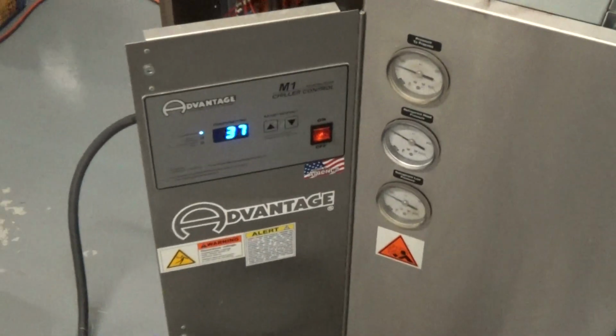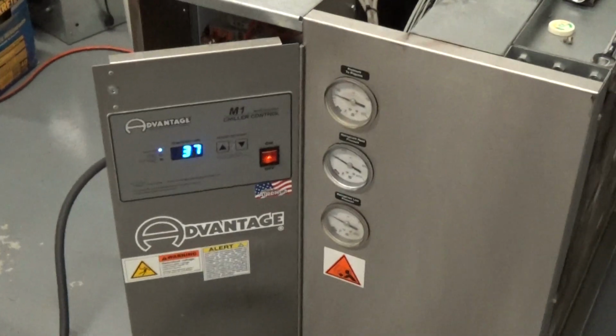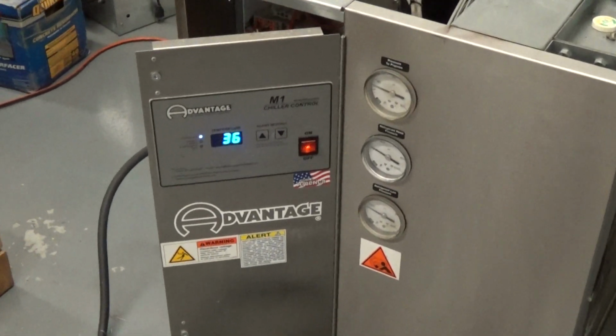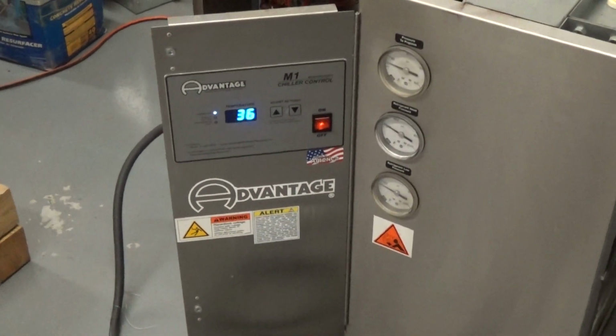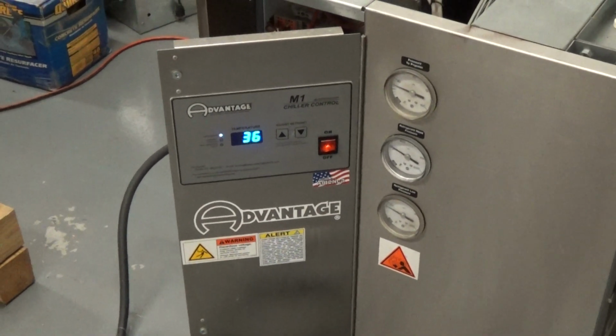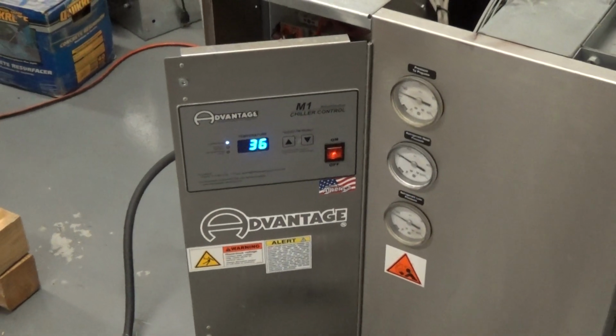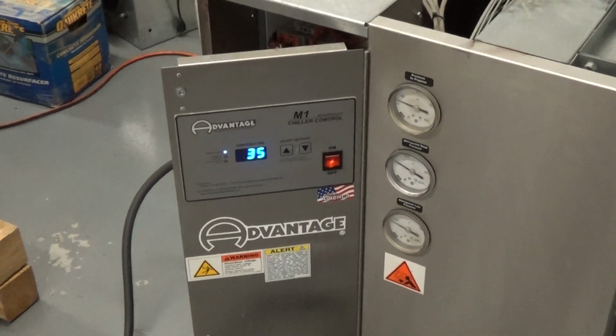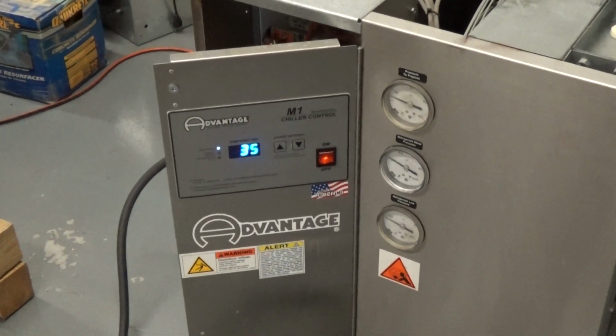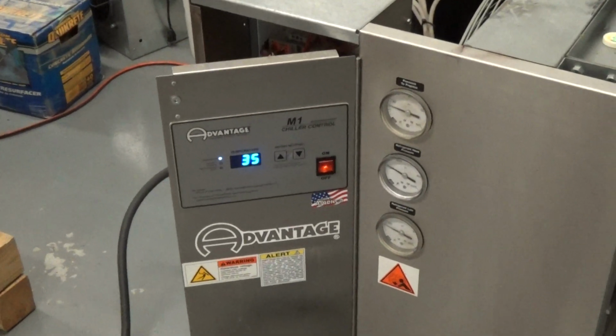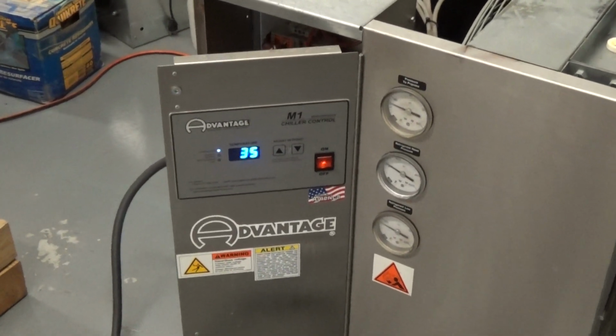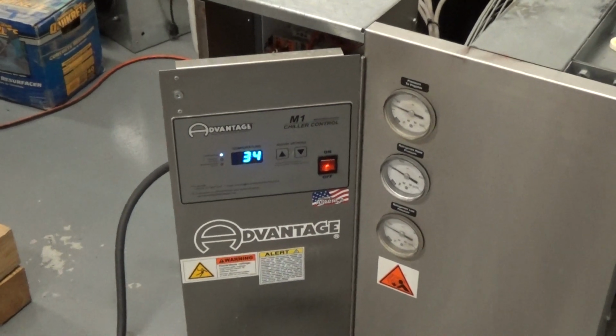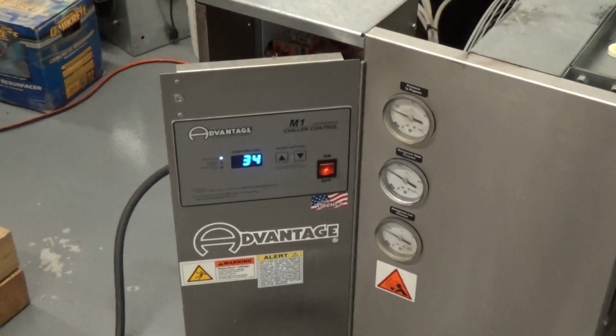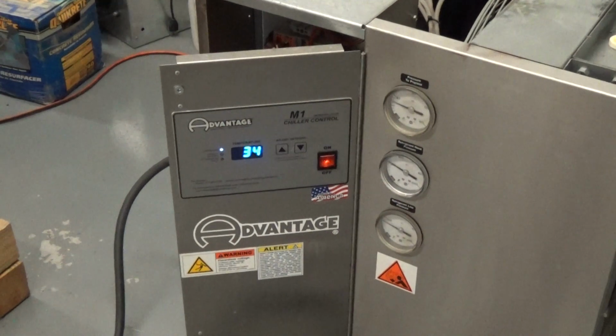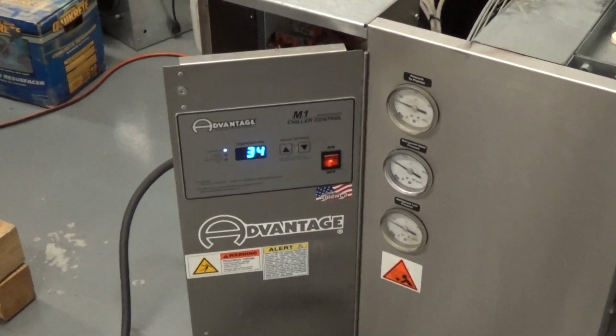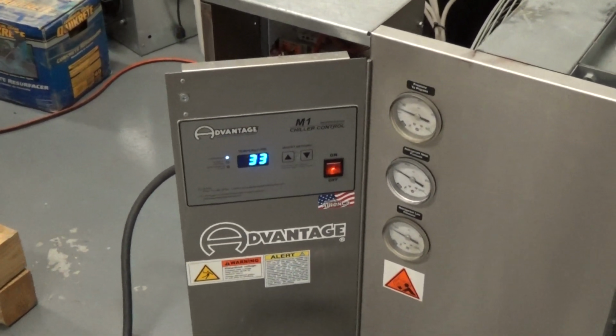So all controllers have a built-in differential or hysteresis, if you want to call it. This one, I think it's minus 3 or 4 degrees, plus 2. It's like a 5 or 6 degree differential, and that's normal on a chiller. Some chillers it's more like 8. So what does that mean? It means we're going to get to 20 and we're probably going to go below 20 by 2 or 3 degrees. As we get close to 20, you'll probably hear the hot gas bypass or the capacity control kick on.